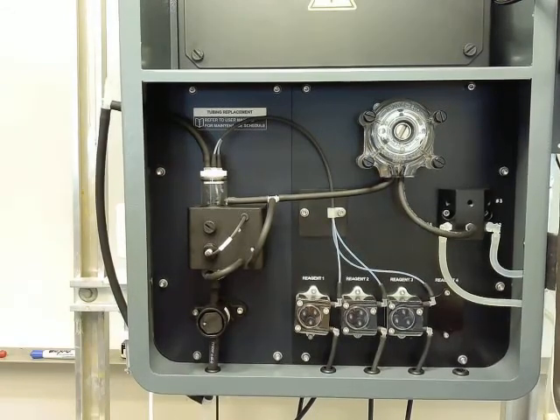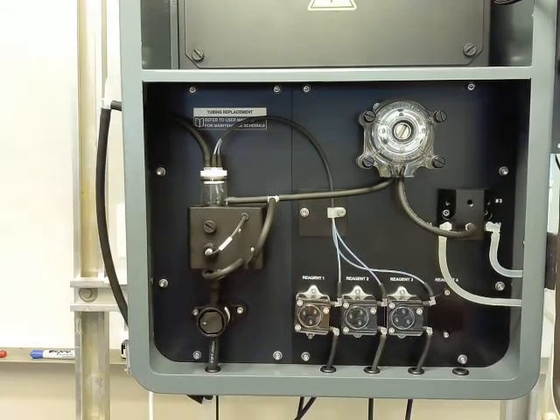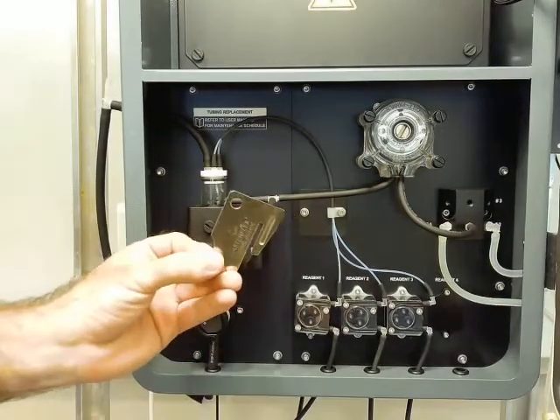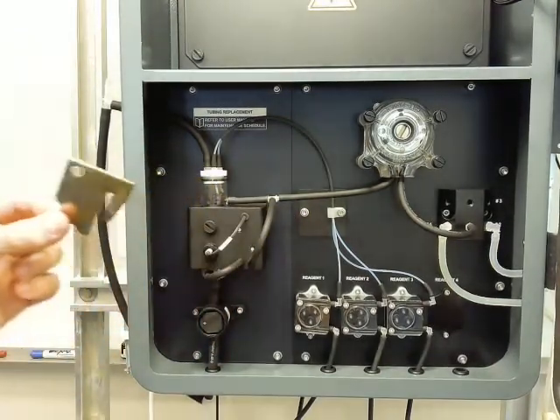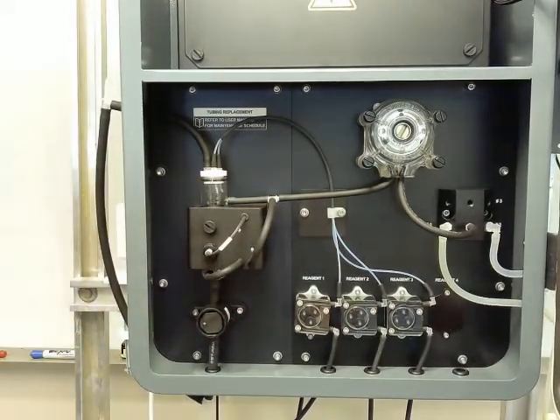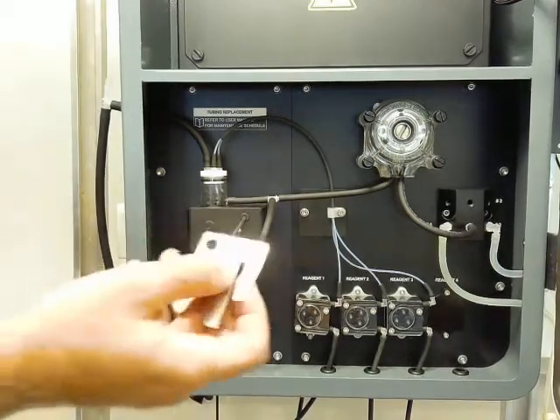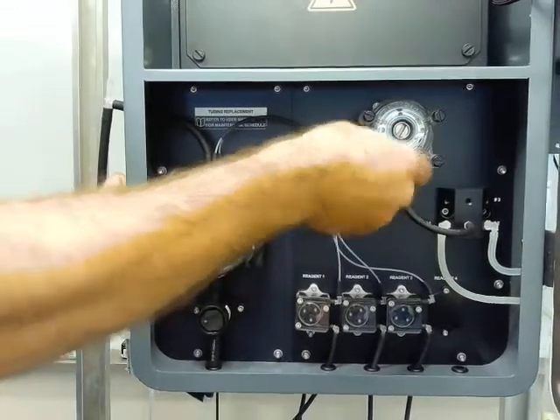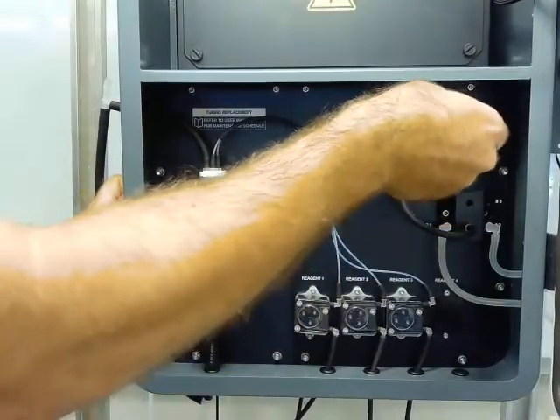So for the sample pump tubing, the kit comes with this little sample pump tool, which is handy. Not required, but makes it a much easier process. First thing we can do is loosen our 4 screws on the pump head and take them out.